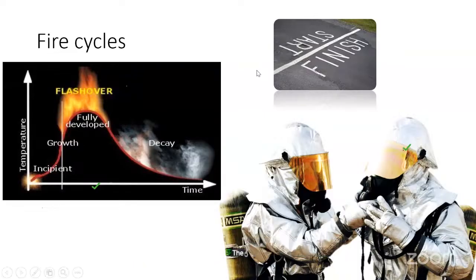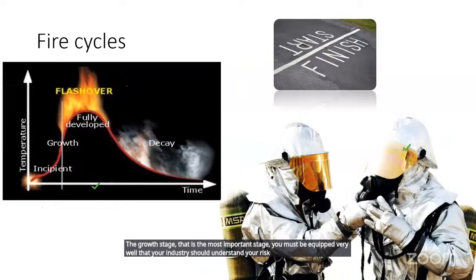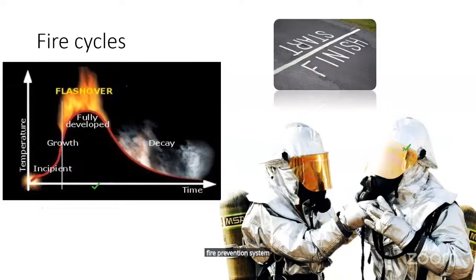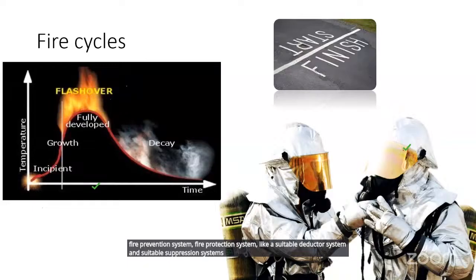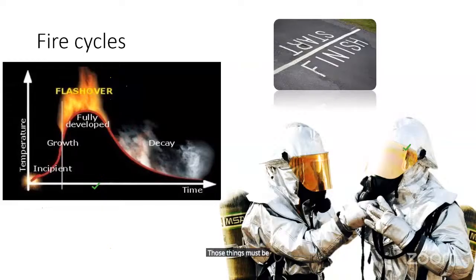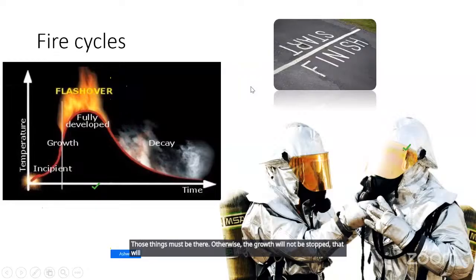The growth stage is the most important stage. You must be equipped very well. Your industry should understand its risk factors, fire hazard factors, quantification of fires, and assessment of risk factors. Accordingly, you have to establish fire prevention and fire protection systems, like suitable detector systems and suitable suppression systems. Not only establishing the systems, you have to maintain them, and you have to keep people to operate them in case of emergency. They must be trained very well. Those things must be there. Otherwise, the growth will not be stopped and it will reach the fully developed stage. That is the message I want to pass on to you in this slide. Next slide, please.